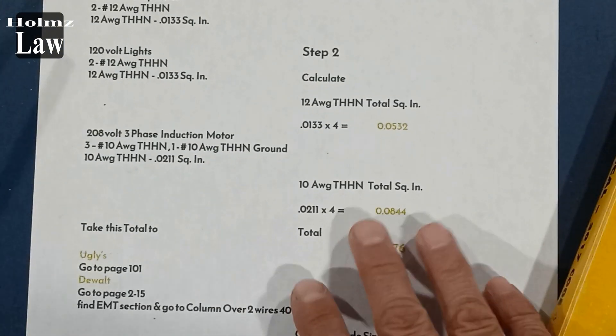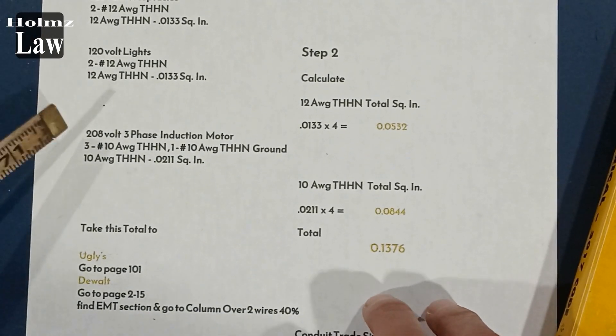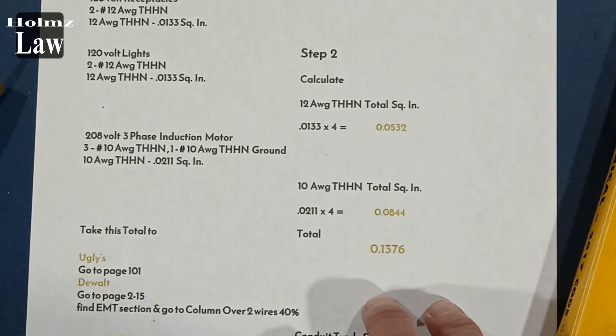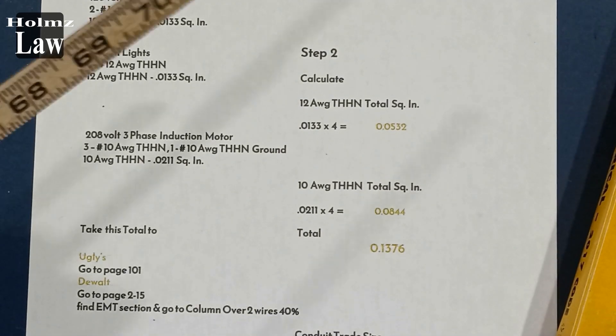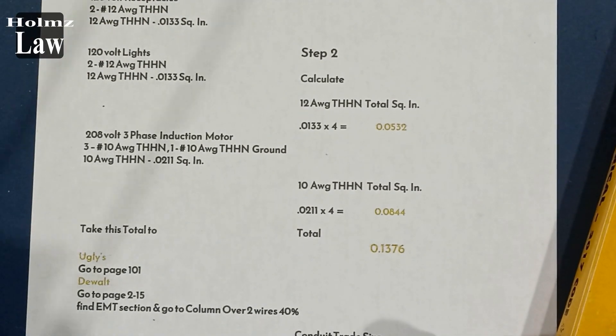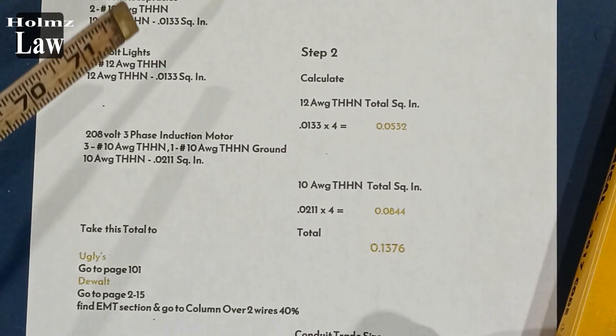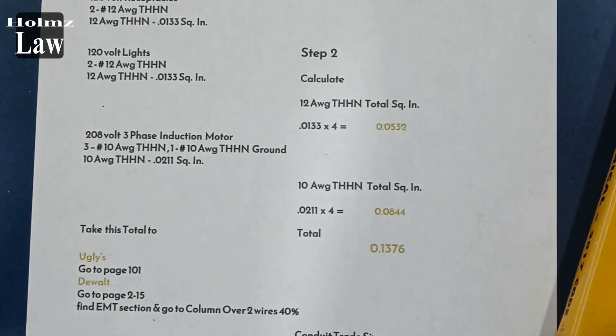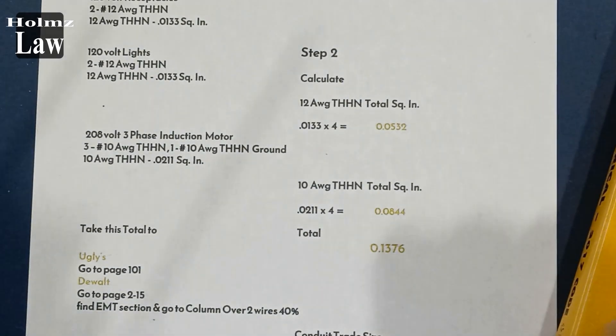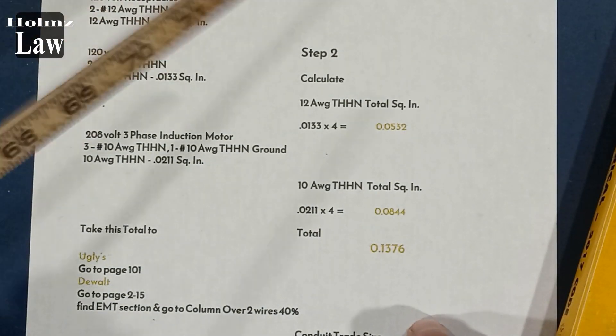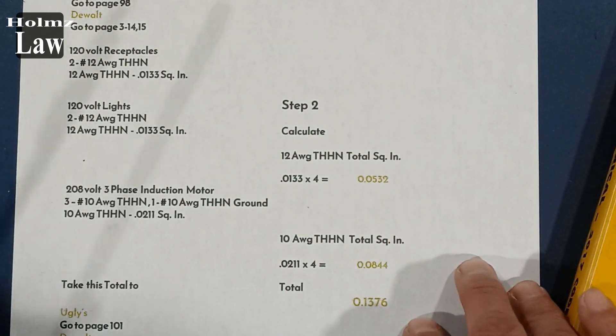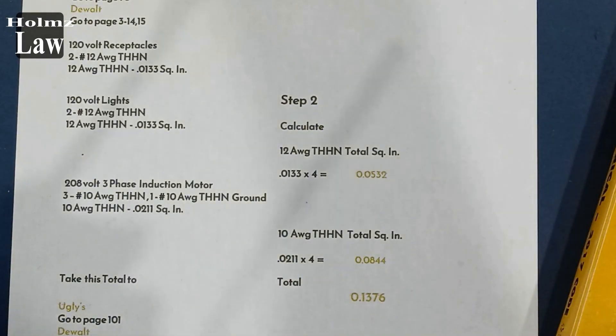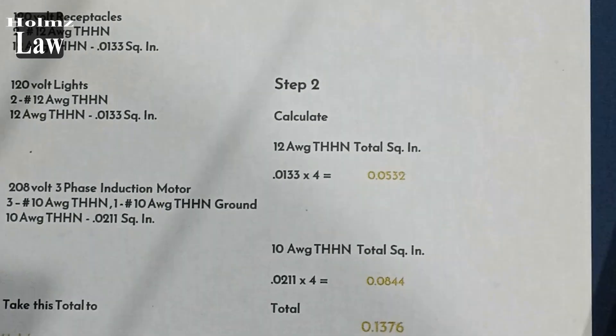For the motor circuit, it's a three-phase 208-volt circuit. We're running three 10-gauge THHN wires, and we're also running a number 10 ground with that. So for this example, the motor circuit includes a ground — you can adjust your own calculation in the field.